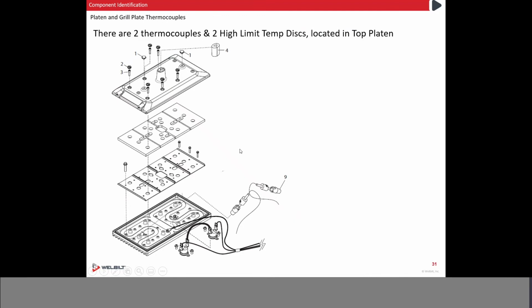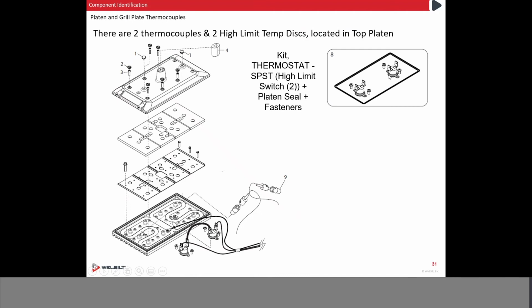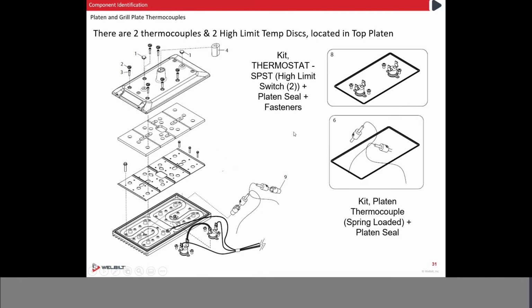In order to get to them, we have to separate the Platen from the cowl. Every time you separate the Platen and cowl, we have to replace the gasket. So when you order a kit, you get two safety thermostats and a gasket. Or if you order a thermocouple kit, you get two thermocouples and a gasket. This way you replace them all at the same time.